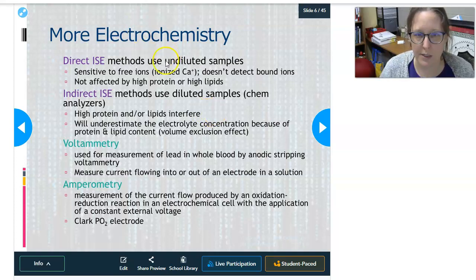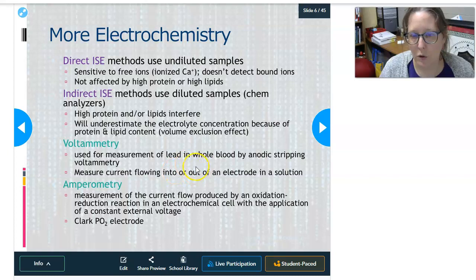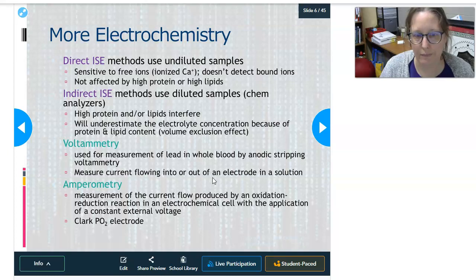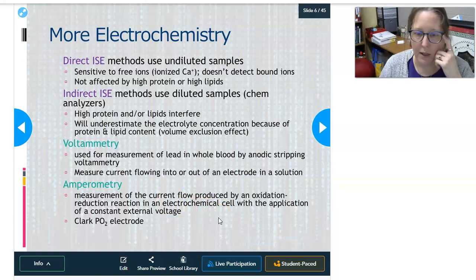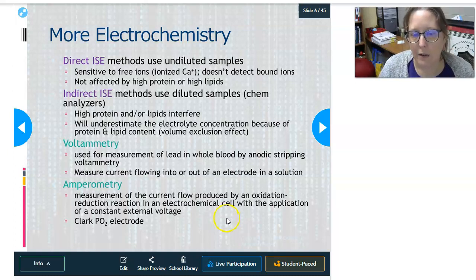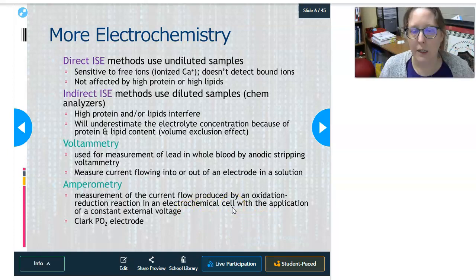A couple more things in electrochemistry: voltammetry can be used for measurement of lead in whole blood by anodic stripping voltammetry. It basically measures the current flowing into or out of an electrode in a solution — not widely used, but it's a way to measure lead. Amperometry measures current flow produced by an oxidation-reduction reaction in an electrochemical cell with a constant external voltage applied. An example is the Clark PO2 electrode, which is how we measure PO2, partial pressure of O2, found in the ABG analyzer.